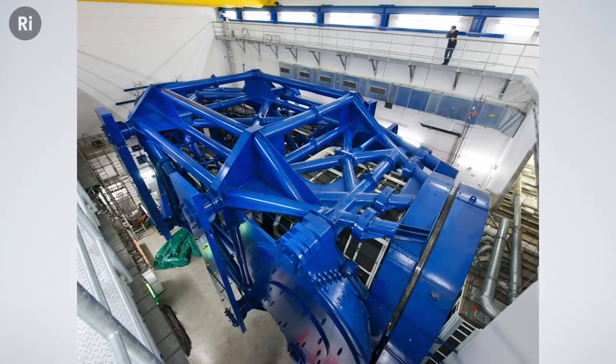The beam line on that gantry is kind of shaped like a question mark, so it rotates all the way around the patient. Because of the size of the magnets that you have as part of that accelerating structure, these devices are big. The smallest gantries are about 100, 150 tons.